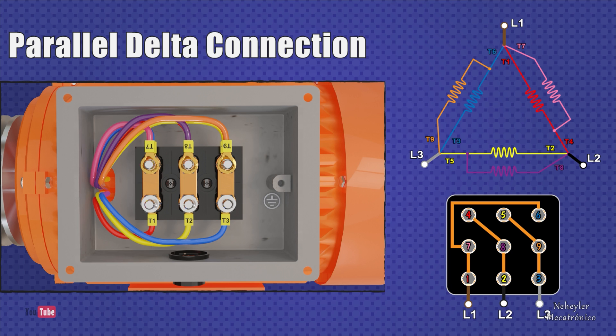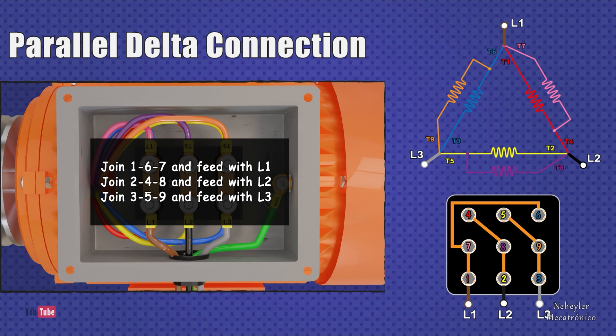Terminals 7, 8, and 9 are connected to Terminals 6, 4, and 5 respectively. The power cables are attached to the first three terminals. In summary, Terminals 1, 6, and 7 must be joined and fed with L1. Join Terminals 2, 4, and 8 and feed with L2. Join Terminals 3, 5, and 9 and feed with L3.